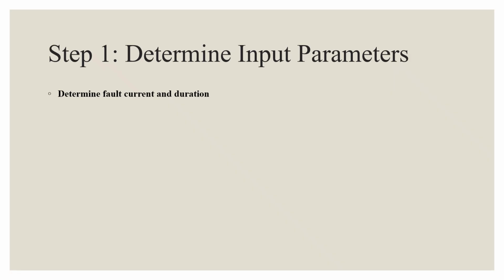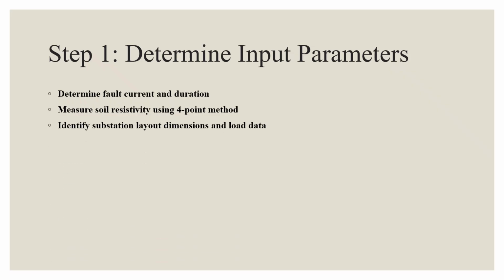The first step in designing is to determine all input parameters like fault current and its duration, soil resistivity from the 4-point test, and the physical dimensions of the substation area. Accurate field measurements are important because soil resistivity varies with moisture, temperature, and depth.